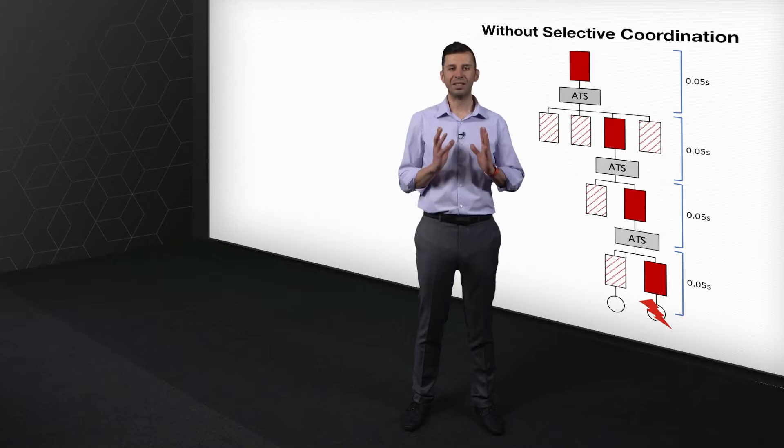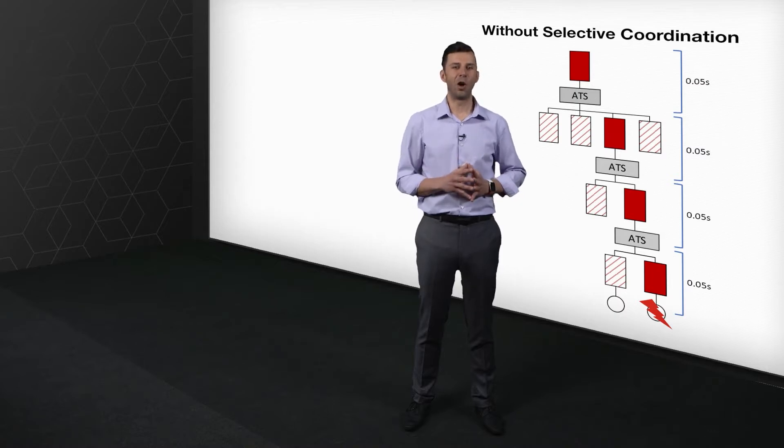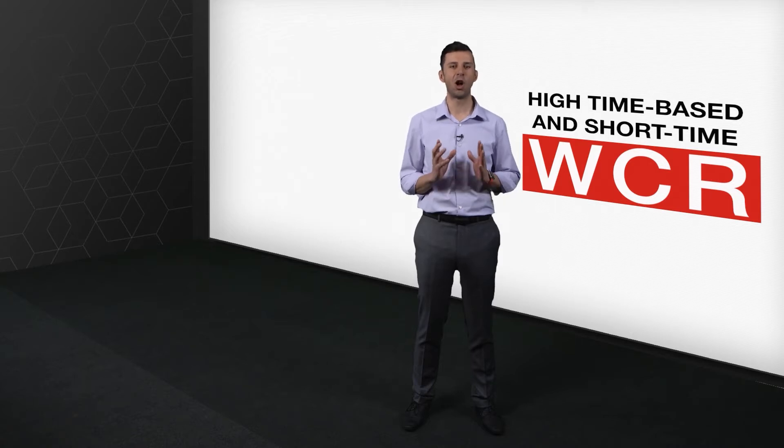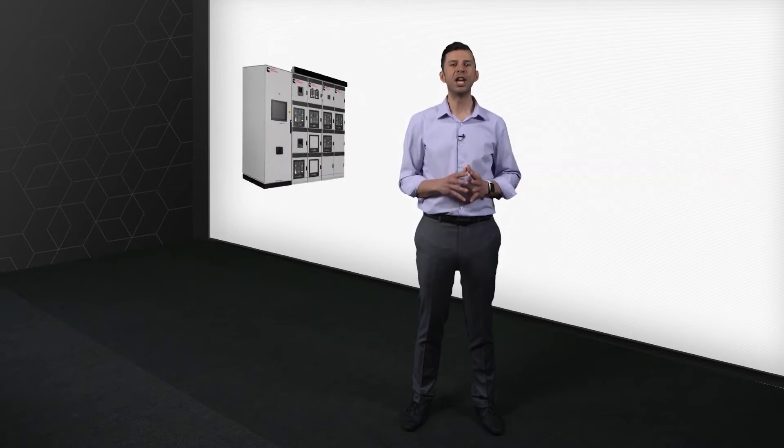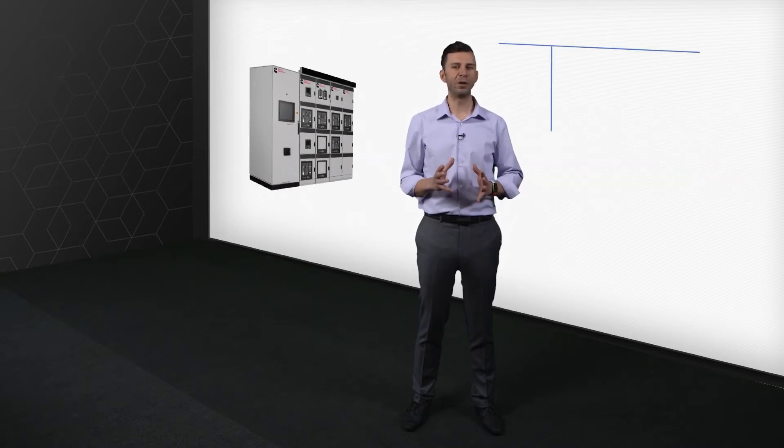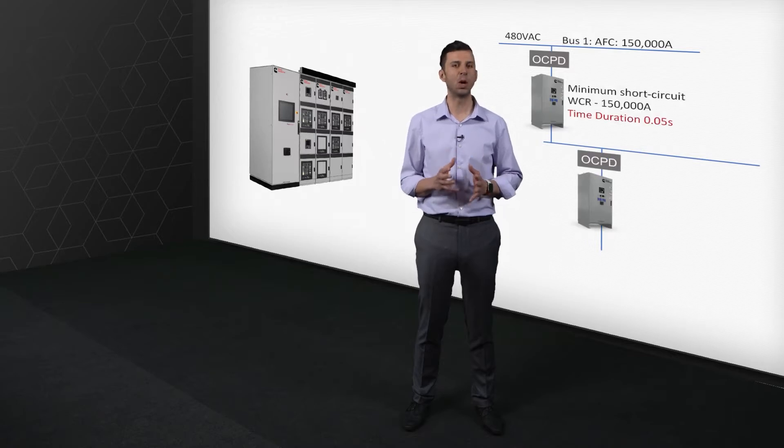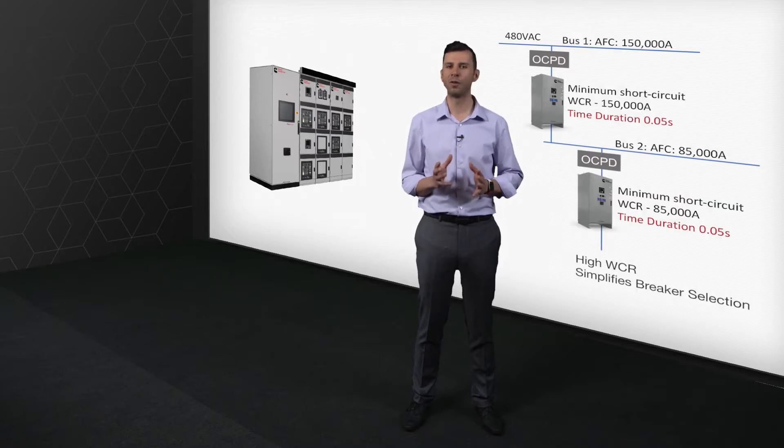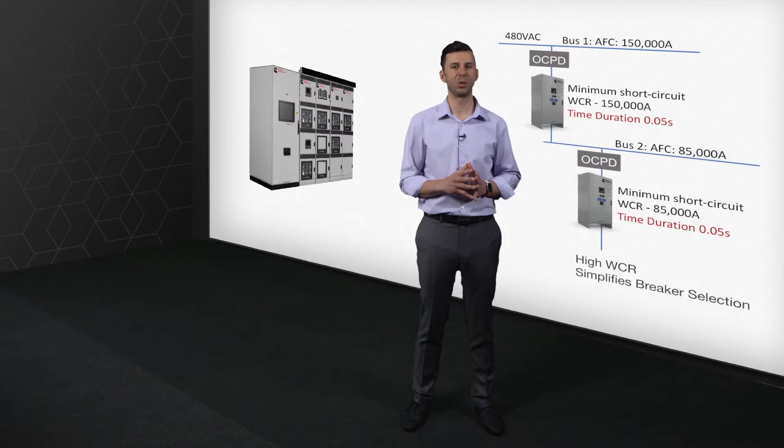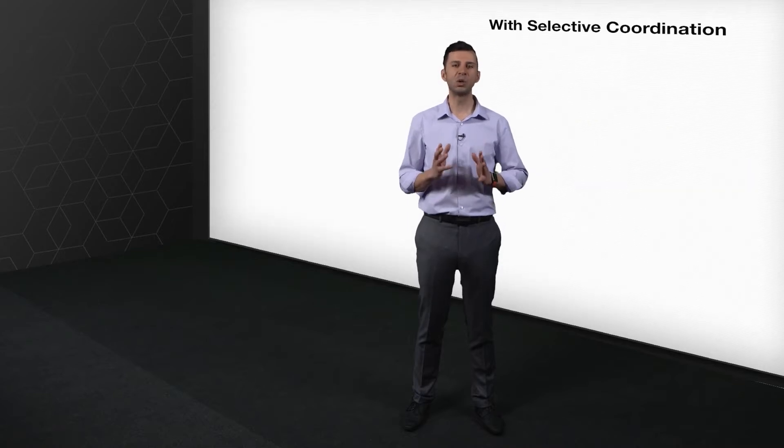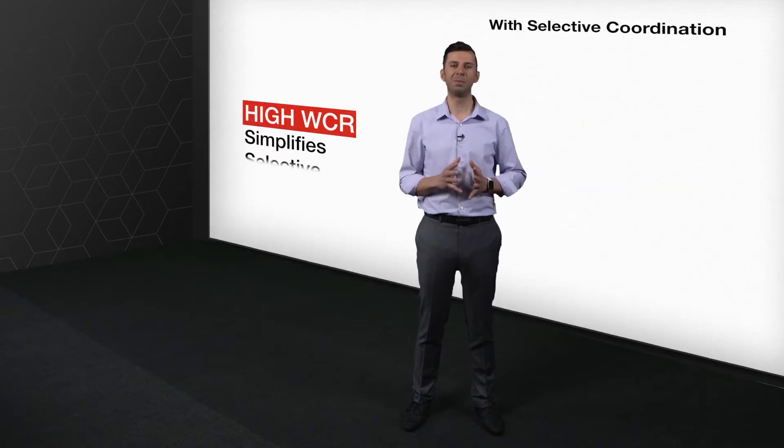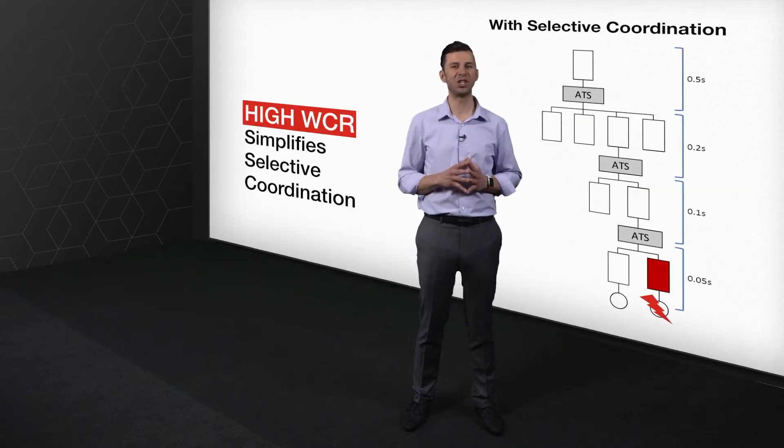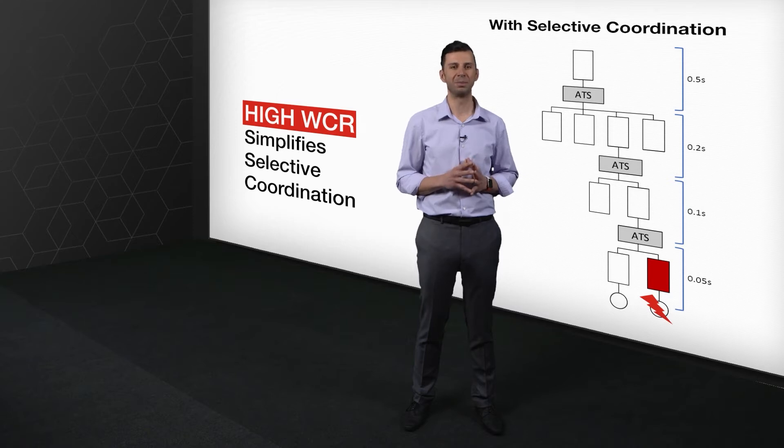To help you solve all these challenges, a high time-based and short-time WCR on the X-Series transfer switches give you the freedom to select a generic UL listed overcurrent protection device to protect the transfer switch, and also enables and simplifies selective coordination strategies throughout your system.